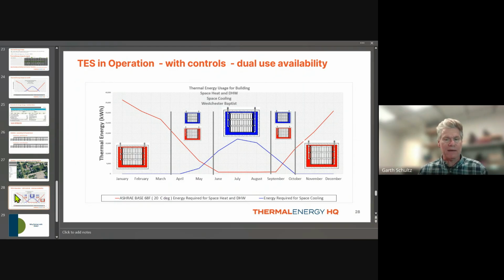And then, of course, in the summertime, all space cooling, you're going to be banking chilled water or cold water to feed the liquid to air heat pumps within the facility. Back into the fall season, once again, you want both energies available to you. And then in the winter, where we're at right now, it's all space heat.